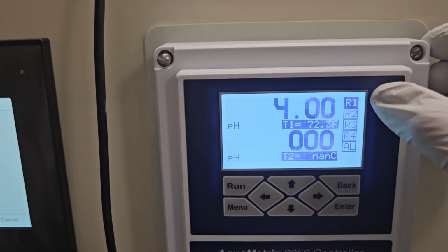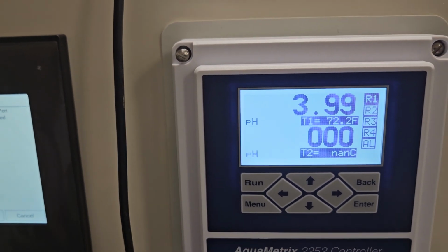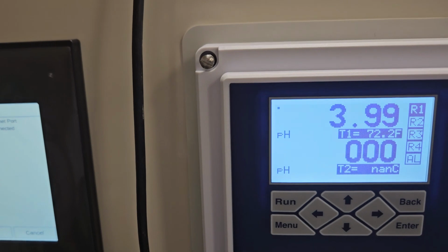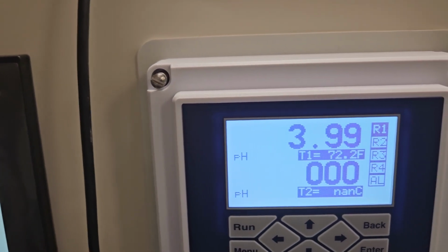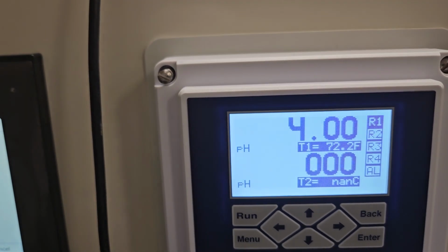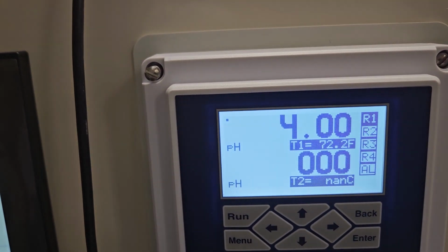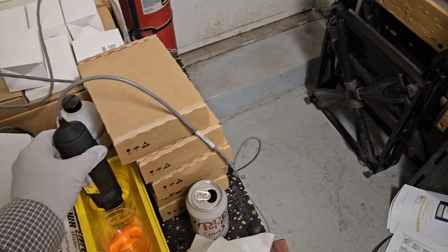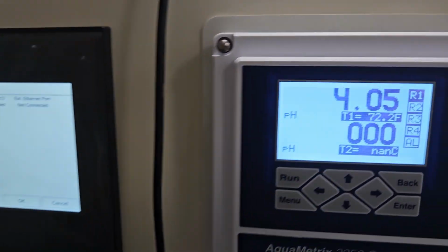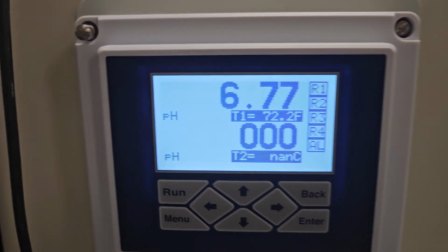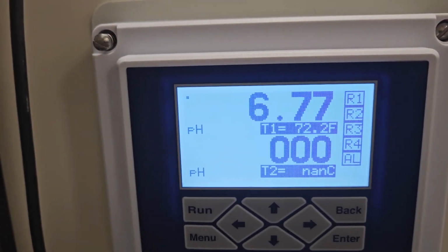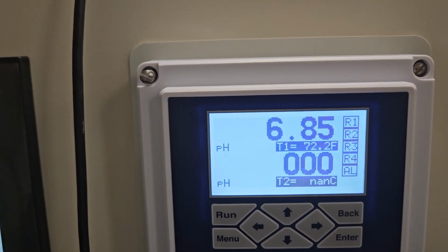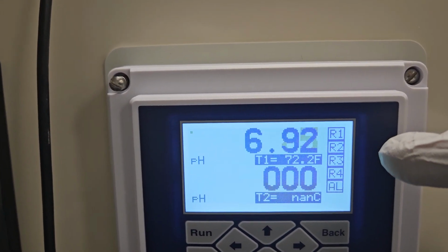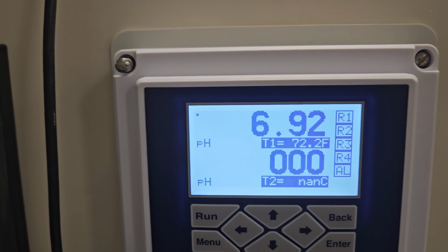At this point, at 4, you notice that relay 1 is on. If you recall in the previous video, we set that to go on at 6.4 and below. So it's below that 6.4 reading and turns off at about 6.5. If I put the probe back into a higher pH solution, like if I was adding caustic or lime to this process, pH would be rising. Eventually it rises above the off point, and now the relay has turned off. My set point to turn off was 6.5, it's gone above that, so that's why the relay has turned off.